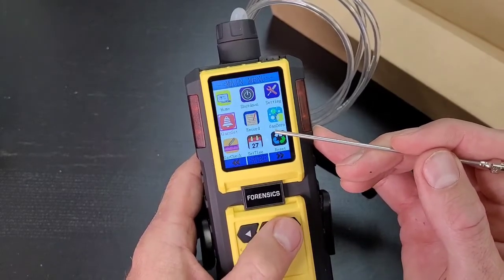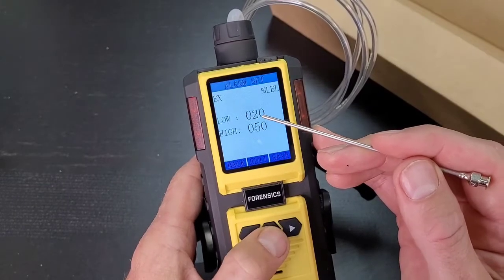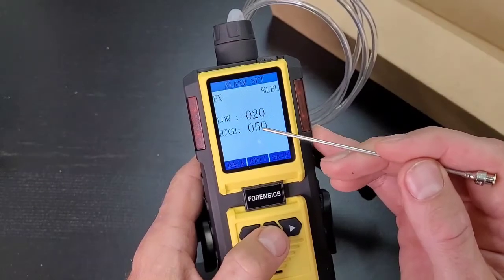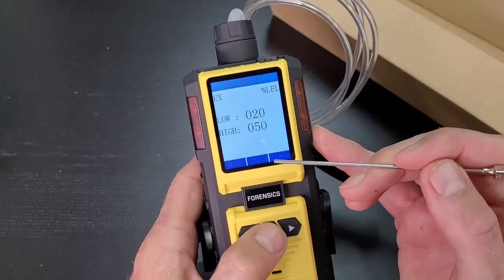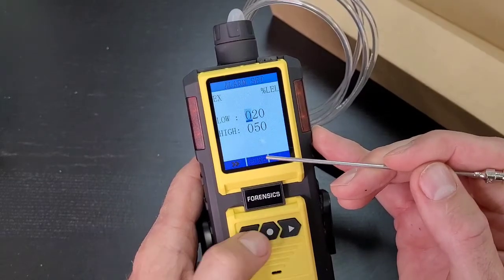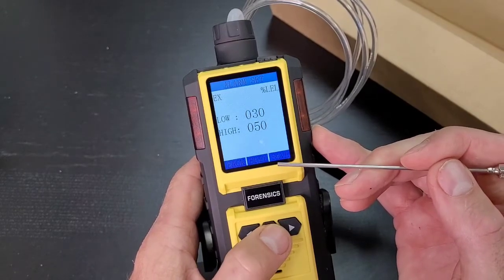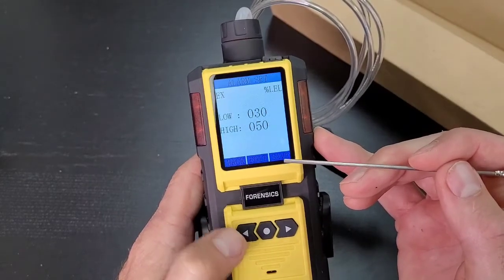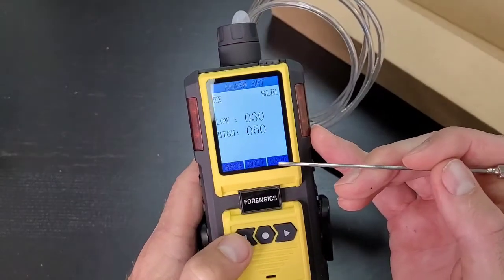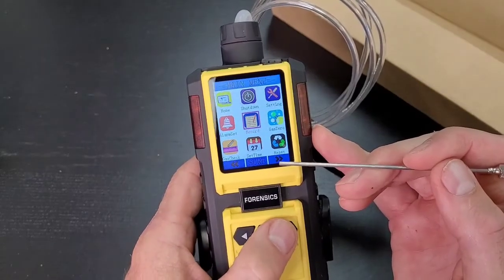You can change your alarm settings depending on where you want the alarms to set. Twenty is the 20% LEL is the low alarm, high alarm, you just go to edit and you scroll through and you can change. Sure, save, bang. It's quite intuitive. I don't have to do this tutorial but you can see how easy it is.